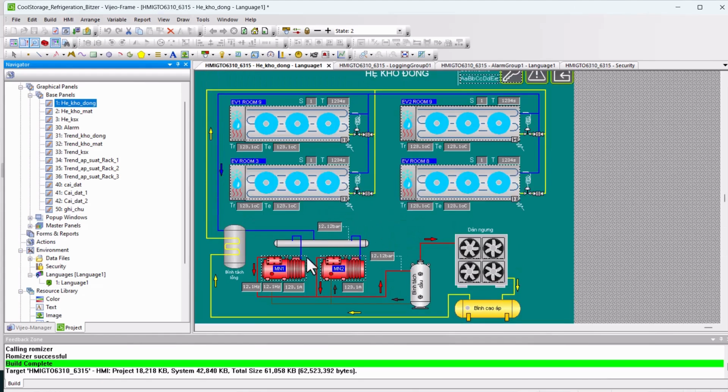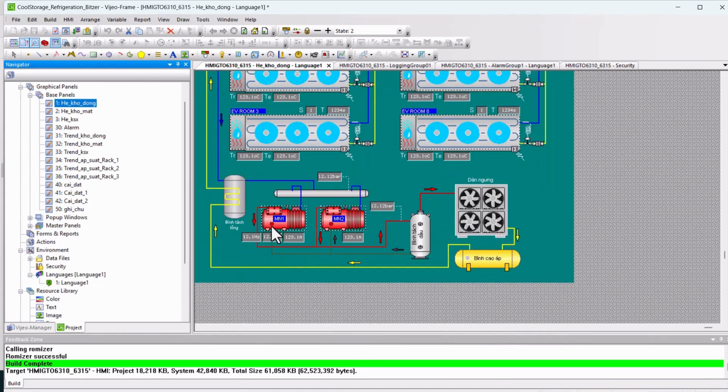Based on the suction pressure, the compressor will be controlled to run, stop, and control capacity to stabilize the suction pressure, and discharge pressure. Based on the discharge pressure, we control the evaporative condenser to turn on and off. The number of fans will follow.